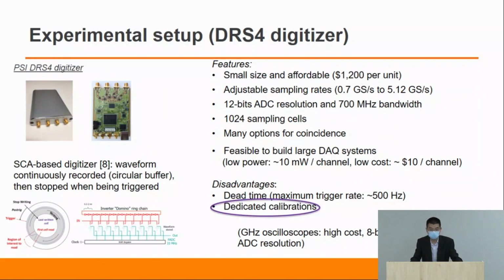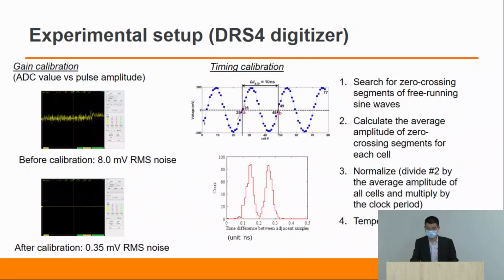Just as I mentioned, this DRS4 digitizer needs a dedicated calibration to get the best timing resolution. I will talk a little bit about how the calibrations can be done. There are two calibrations. One is the gain calibration, and the other one is the timing calibration. The gain calibration should be done before the timing calibration.